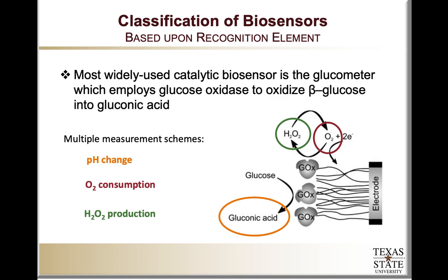Later on in the 1960s, they developed electrochemical biosensors for glucose measurements, and the first system that was commercialized came out in the 1970s, by the company Yellow Springs Instrument. It was an amperometric sensor that measured current developed by utilizing hydrogen peroxide, which we'll discuss in a second. Since then, there's been a lot of development in the field, including the integration of these glucose meters with insulin pumps, which can help have a closed system of detection and therapy in one single unit.